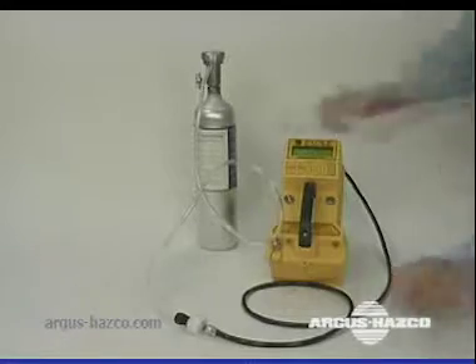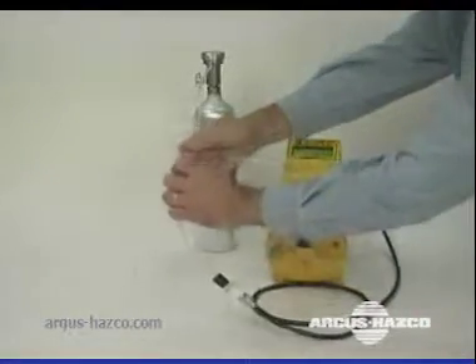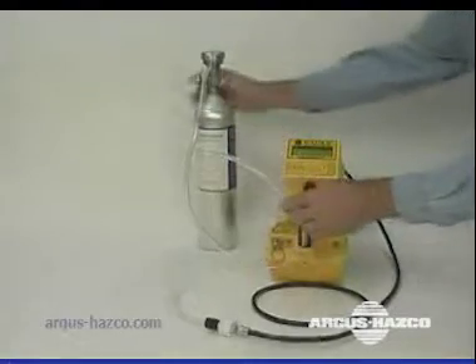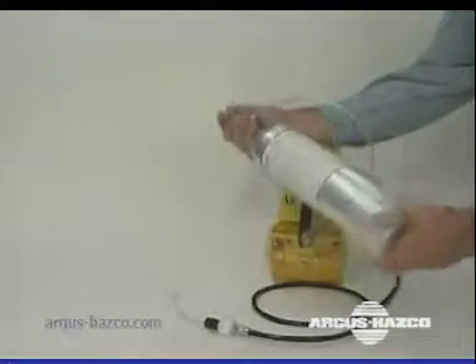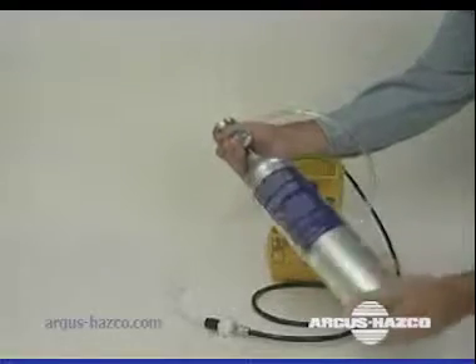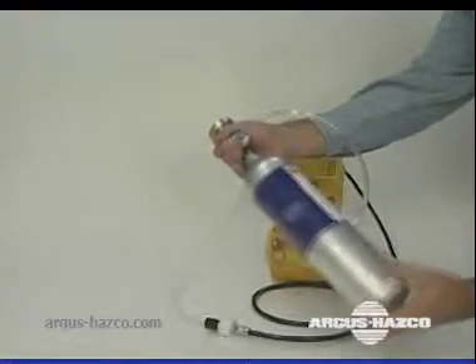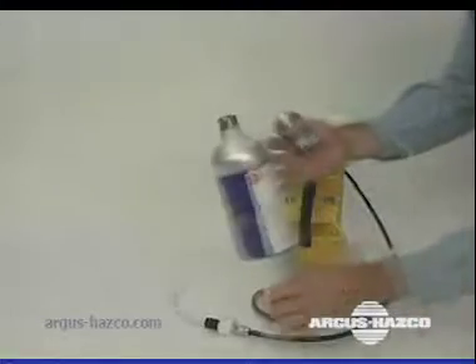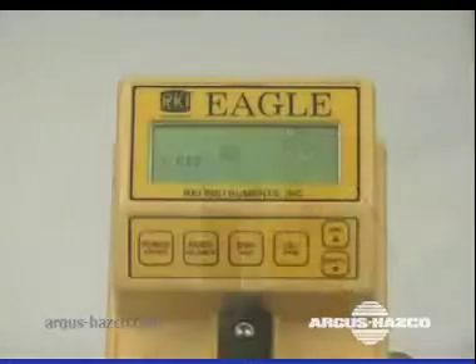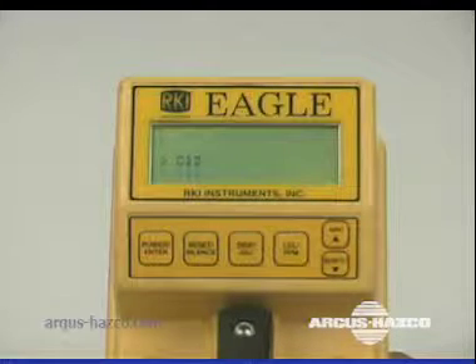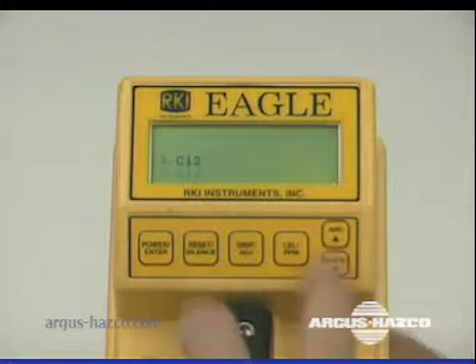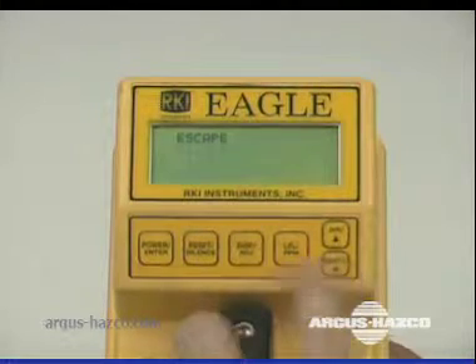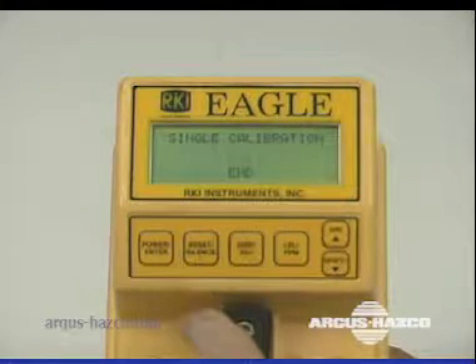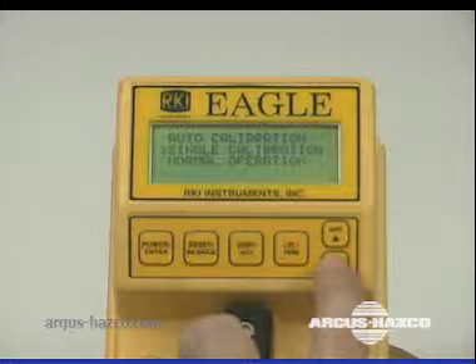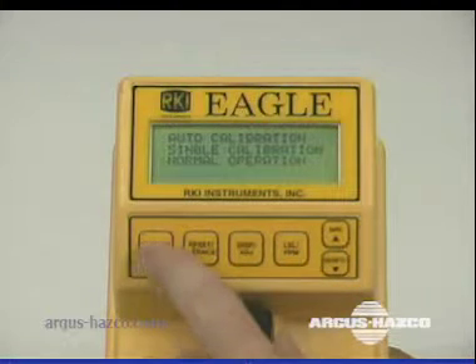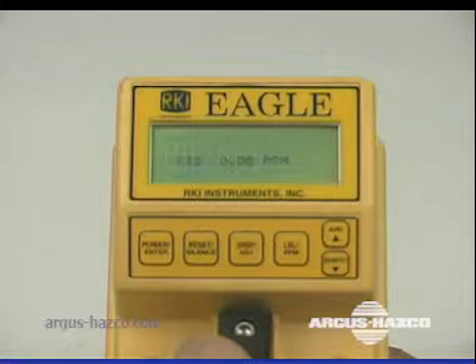Next, disconnect the tubing from the probe. Unscrew the calibration cylinder from the regulator. With the single calibration menu displayed, press the down button until the prompt is next to escape. Then press the Enter button to return to the calibration menu. Press the down button to place the prompt next to the normal operation menu option, and press the Enter button again to return to the normal operation screen.